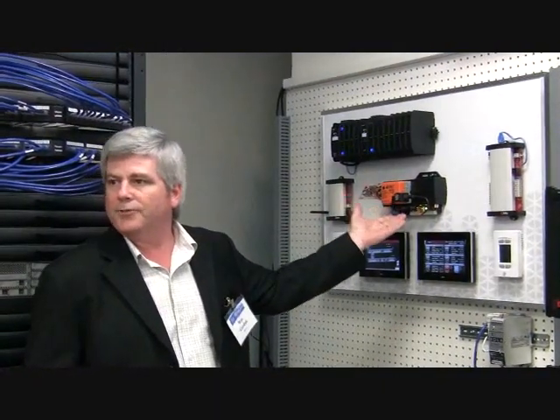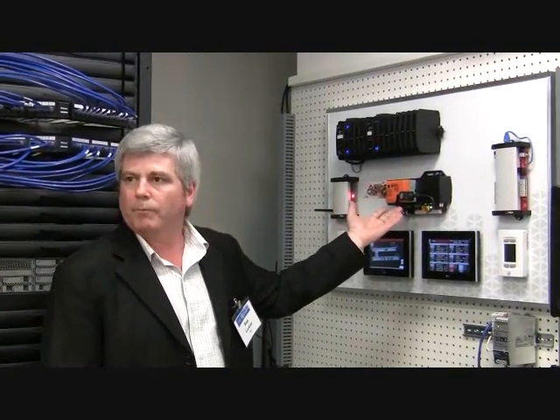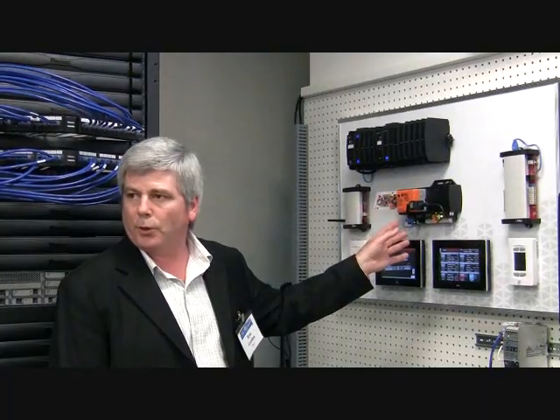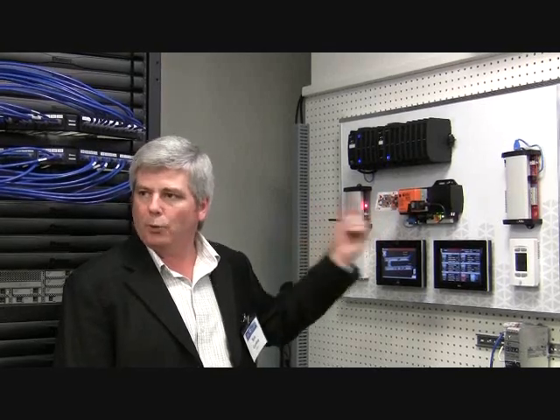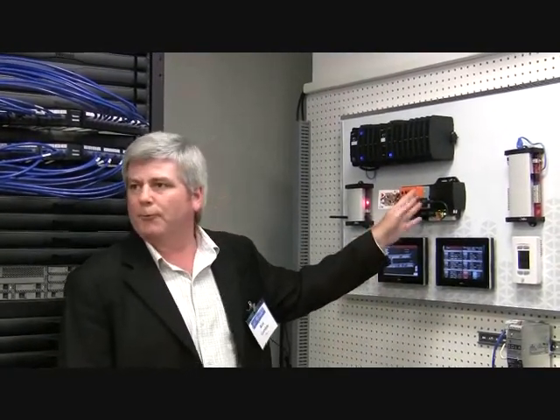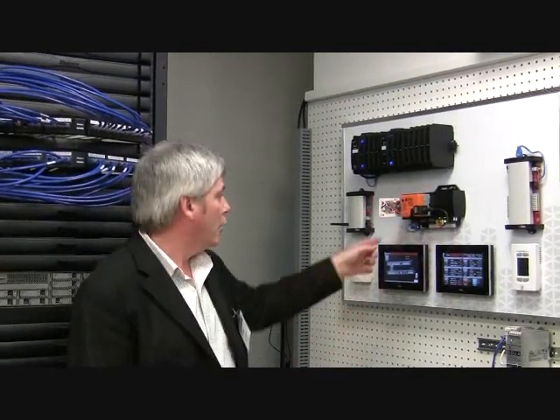This is the HVAC controller that Rick mentioned, that ESC, or the people who have provided it to us here, and Delta Controls manufactured. It's a PoE-powered HVAC controller, a VAV controller box. What it means is normally you would have low voltage plus communication going to one of these units. And to put it in perspective, on a floor plate of a building of this size, normally you'd have about 40 of these in a floor of this size.